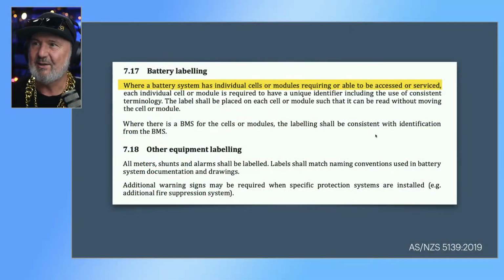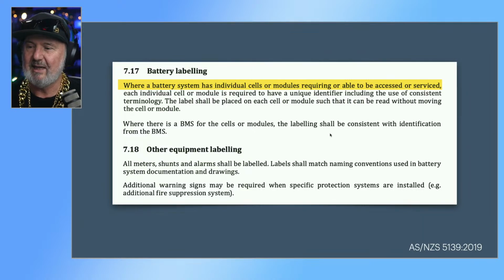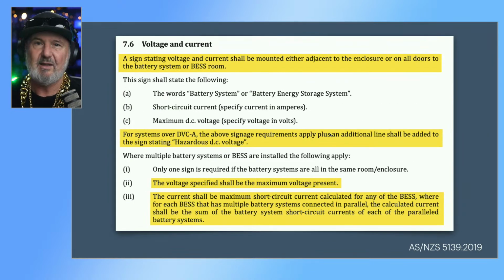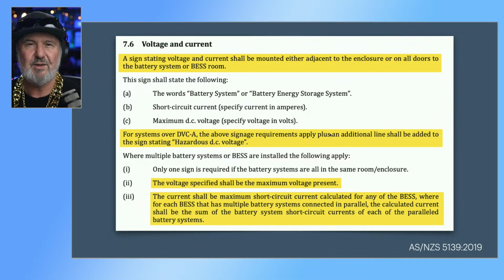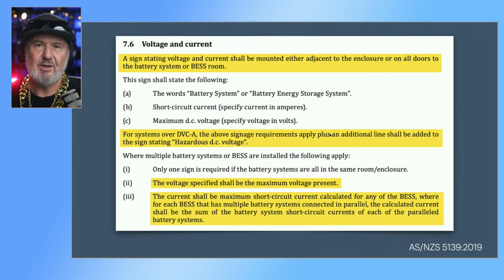There we go. So that's one thing about battery labels. The other question, which is kind of related to labels too, is what do you put on the voltage and current label? There's a requirement to have the maximum battery voltage and short circuit current. Now, I think we kind of did a poor job in writing the standard for this clause because it's sort of written as if every system has accessible battery terminals that you therefore need to know what the fault current at those terminals can be.